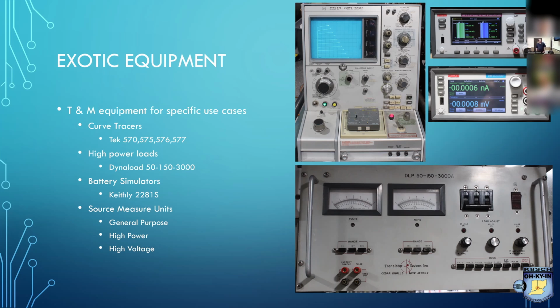Curve tracers, it's a fancy VI plotter. I have needed it every once in a while, needed it to fix the 5200A. There was some transistor leakage, which was why the negative 190 volt rail burned down. The leakage didn't show up till close to rated voltage, so on a low voltage tester it would test fine. Push it to 300 volts, where it was close to breakdown, and then it would show the leakage and actually showed why the part failed.